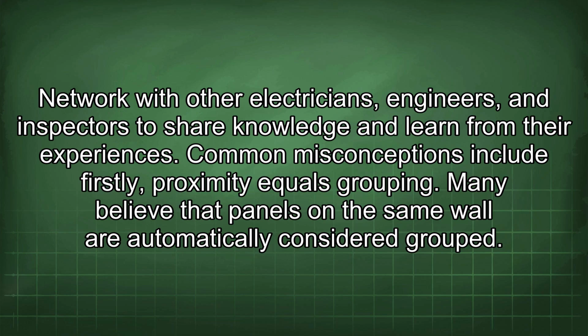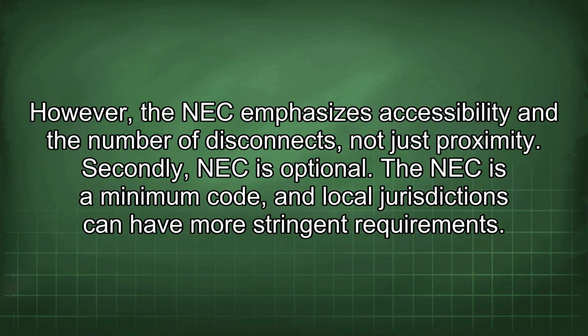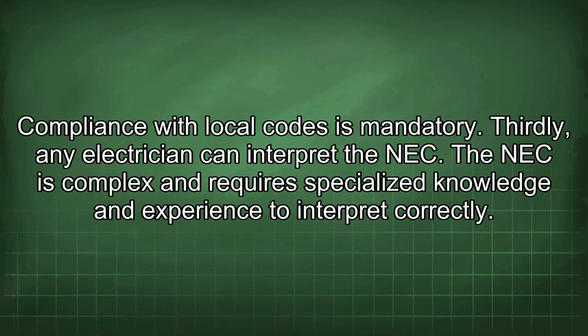Common misconceptions include, firstly, proximity equals grouping. Many believe that panels on the same wall are automatically considered grouped. However, the NEC emphasizes accessibility and the number of disconnects, not just proximity. Secondly, NEC is optional. The NEC is a minimum code, and local jurisdictions can have more stringent requirements. Compliance with local codes is mandatory.